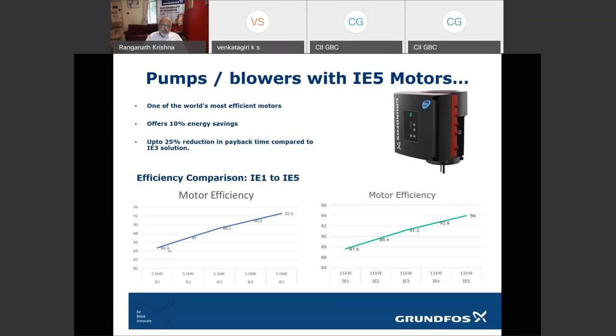So if you see an IE1, which is perhaps the standard in India, it's at 84.7% efficiency at full load, mind you, these are full load efficiencies, and the efficiencies drop considerably at part loads where most of the pumps or blowers work. I compare that to an IE5 motor, which is 92.6, and an IE3, which is at 89.2 for a 5.5 kilowatt motor. And for an 11 kilowatt motor, you see very similar numbers. There's almost a 7% difference between IE1 and IE3, and a 3 to 5% difference between IE3 and IE5 motors.